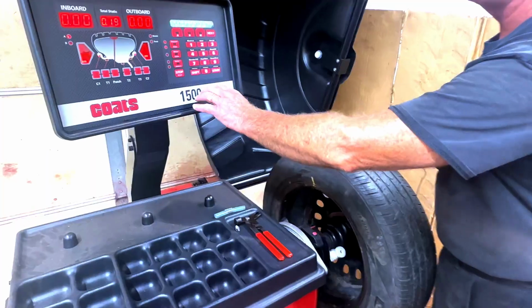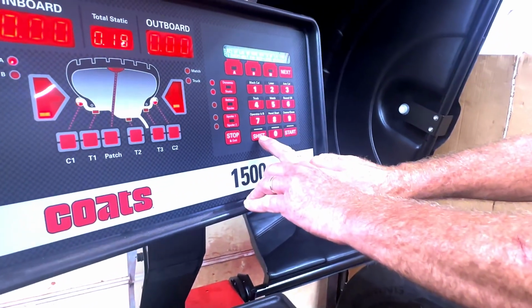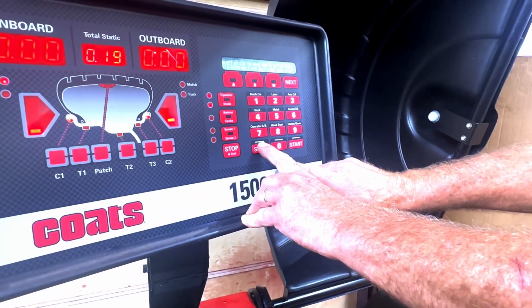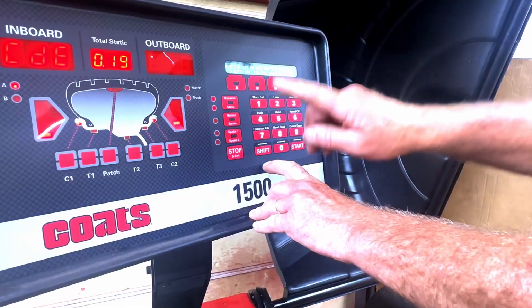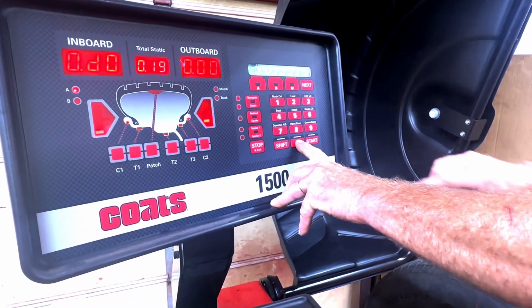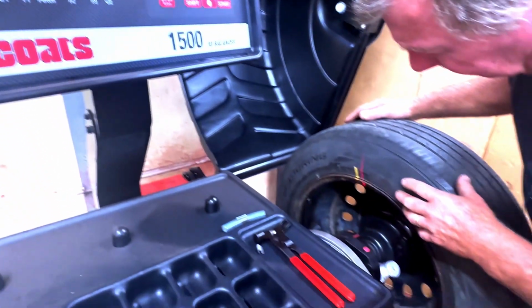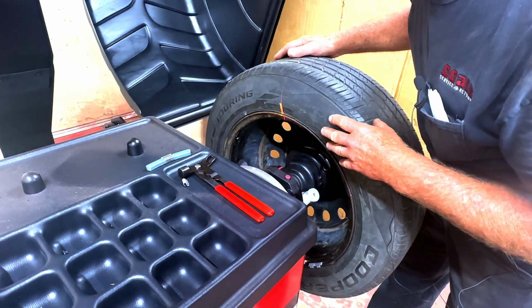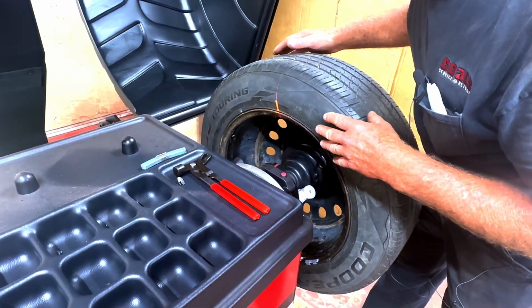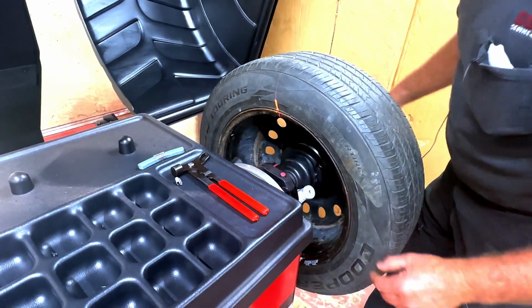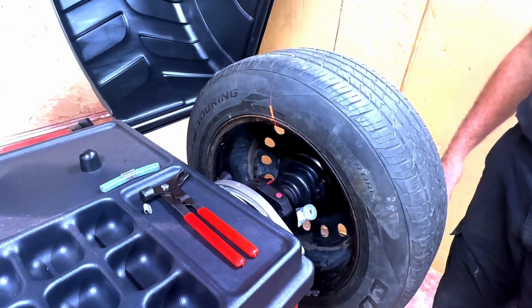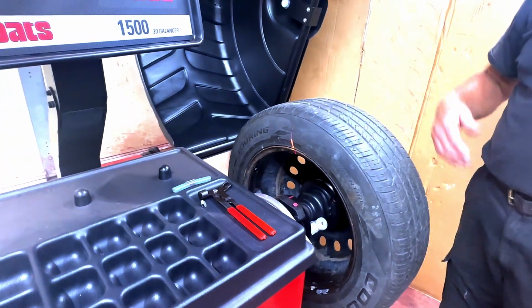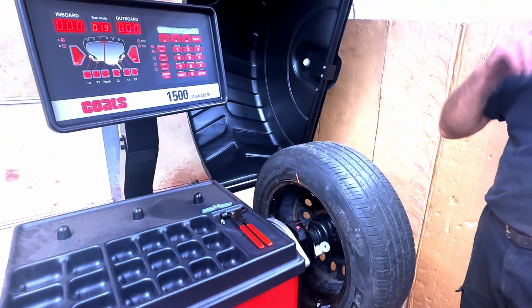You should do that, and there's different ways of doing it. To know what 12 o'clock is, we hit Shift 0, that puts a code in, and put in code 30. That turns on our red line. See our red line, 12 o'clock line? We put the 12 o'clock line on our valve stem, which is in the front, but that's exactly behind the wheel. Now we know.